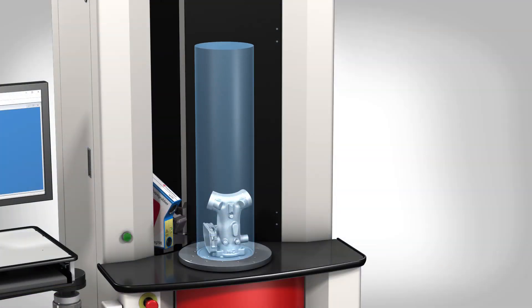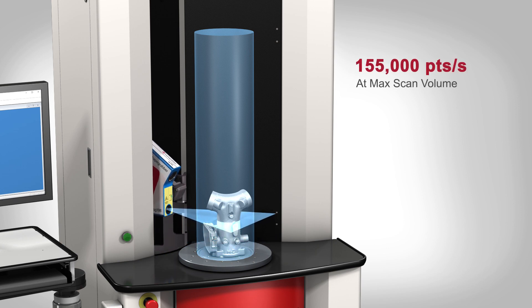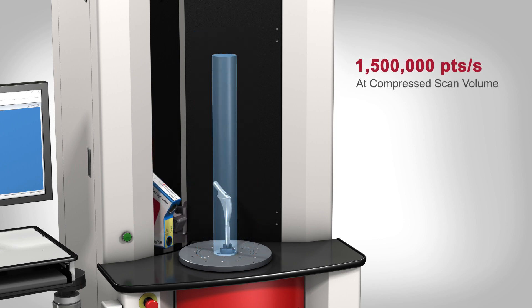At maximum scan volume, the SG198 scan head captures 155,000 points per second. When compressing the scan volume for smaller parts, the capture rate increases to over 1.5 million, offering even faster scanning performance.